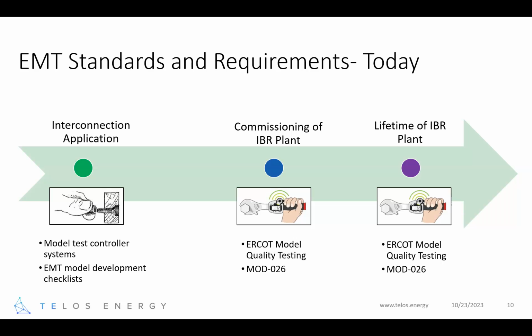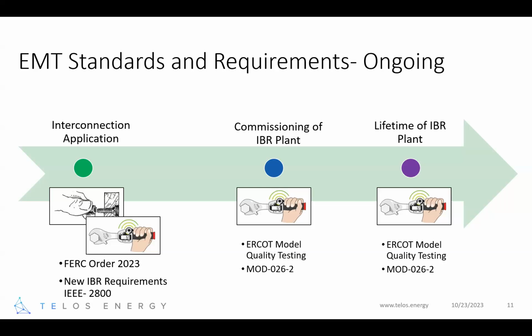During commissioning, we also see really sort of cool in the ERCOT model quality testing, aligning the model itself to what's at the plant and making sure that things are aligned in that regard. And on the MOD front, MOD-026 today doesn't deal with EMT specifically, but MOD-026-2 will align that validation between EMT and the plant response. We also heard earlier today on the interconnection application side of things with the FERC Order 2023. There is some wording in there about EMT models, and actually it kind of leaves it up to the individual grid areas to determine whether or not EMT makes sense for them early in the process. But these are things that we should be thinking about.